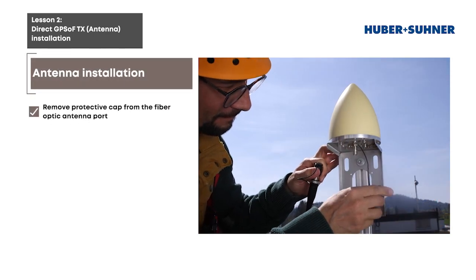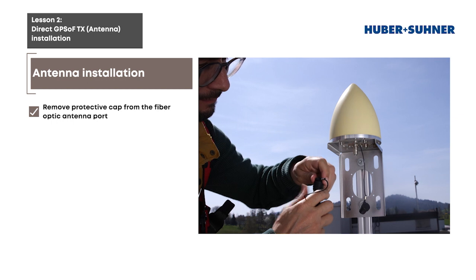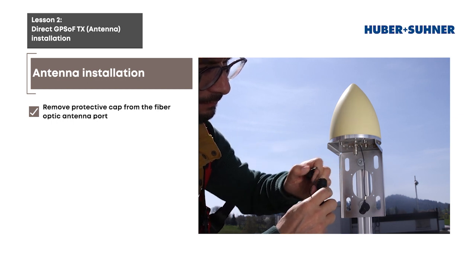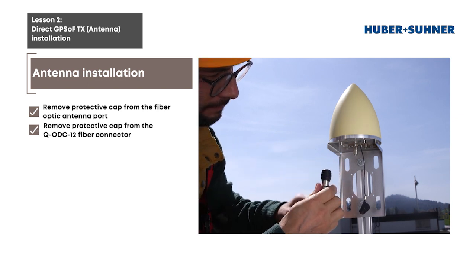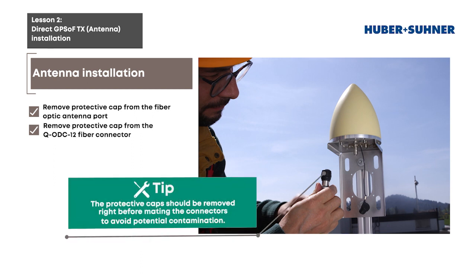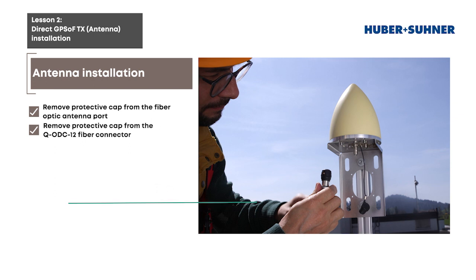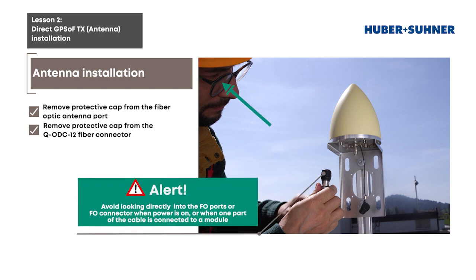Remove the protective cap from the fiber optic antenna port. Then, remove the protective cap from the Q-ODC-12 fiber connector. And here's a helpful installation tip. The protective caps should be removed right before mating to avoid potential contamination. For your safety, you should avoid looking directly into the fiber optic ports or fiber optic connector when the power is on, or when one part of the cable is connected to a module, as invisible laser radiation poses risks of serious eye injury.